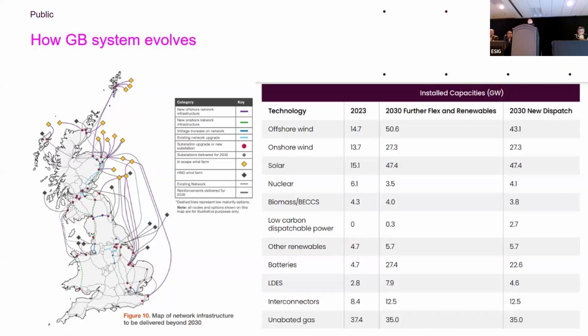We have about a 50 gigawatt system. Generation capacity is about 120 gigawatts. In the last 20 years, we've been through a huge decarbonization. We have more and more renewable generation coming into the system, and synchronous machines are being decommissioned from the system as well. So we regularly operate the system with more than 70% renewable generation penetration level, and our peak record is somewhere around 80%. So we have 80% renewable generation feeding the demand around peak level.